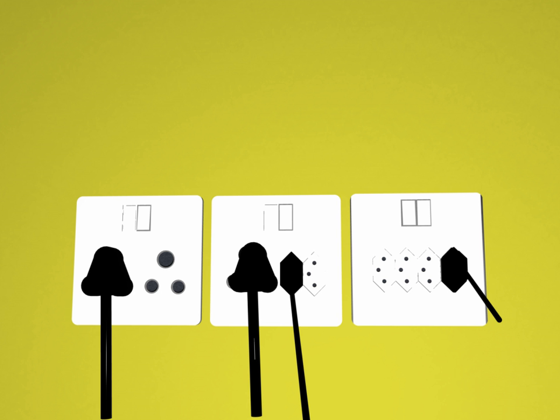The socket has either a 10mm deep recess or a 12mm high rim to exclude incompatible plugs. It ensures that the protective earth pin establishes contact before the line and neutral pins. Sockets are required to have shutters for the line and neutral apertures.